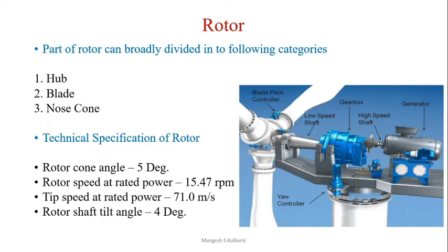Glass fiber reinforced plastic rotor blades, aerodynamically optimized with high strength to weight ratio, good fatigue properties and high elasticity, as well as integrated lightning protection. Blades are mounted on sleeve bearings, which in turn are mounted on an iron hub. A rotor is mounted on the rotor shaft with a through hole for pitch wiring.